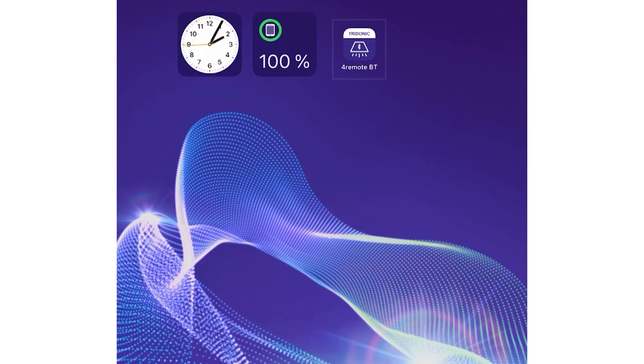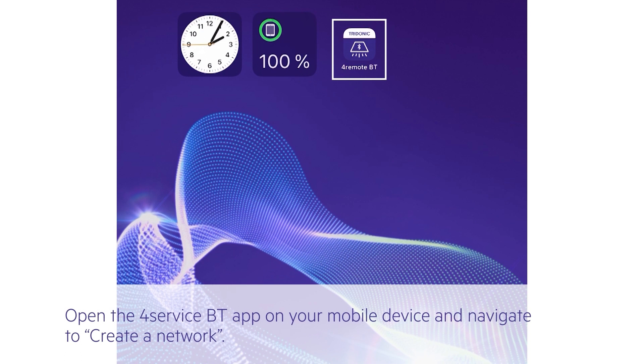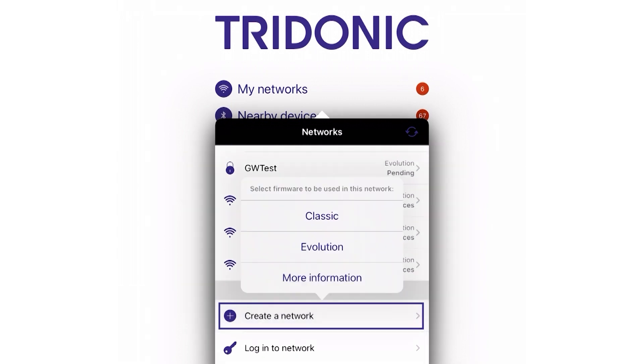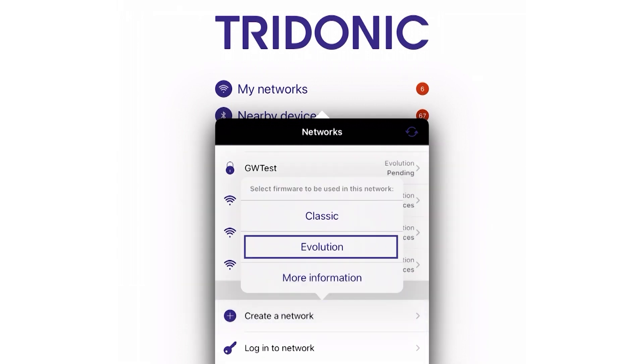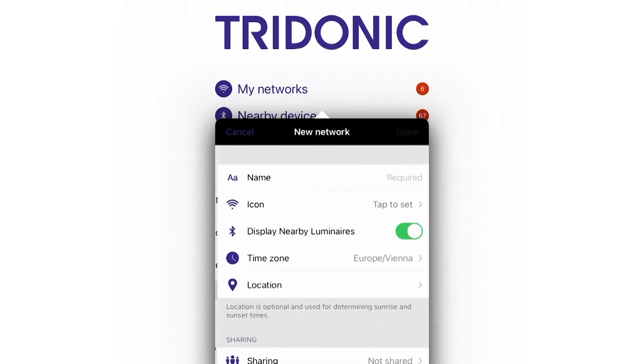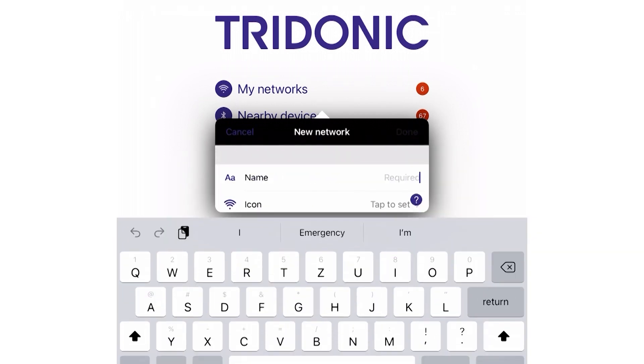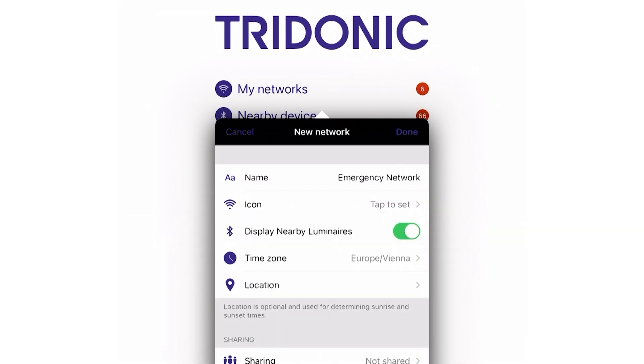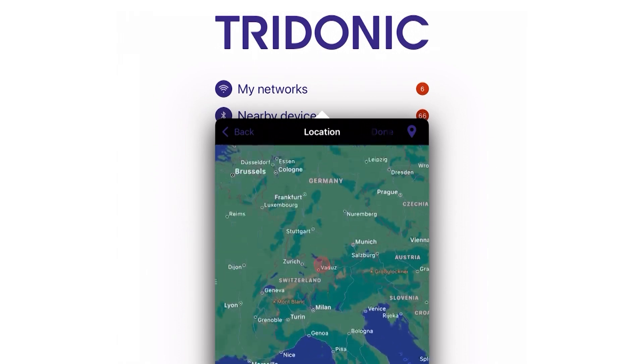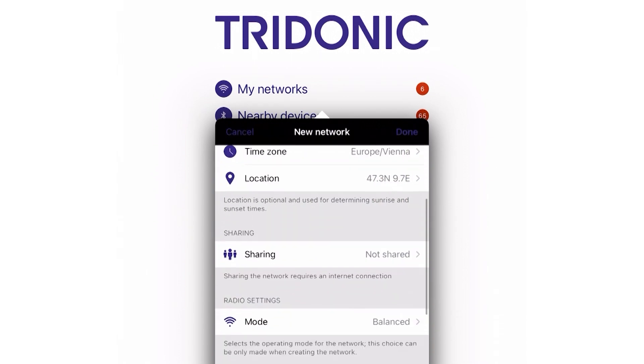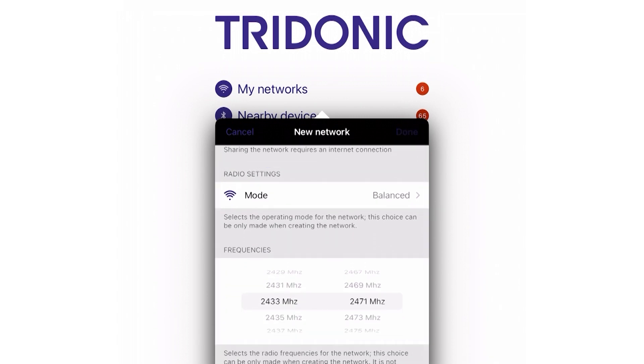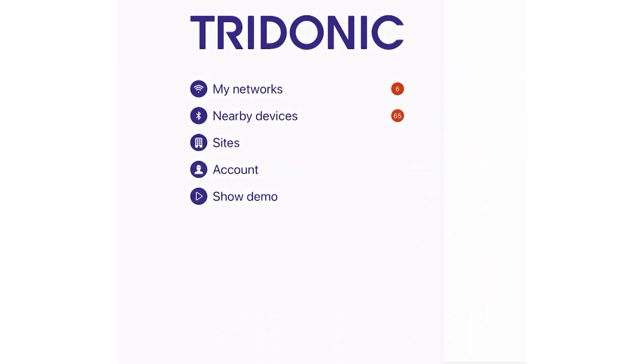First of all, it's necessary to create a network with all emergency devices of the system. To do this, open the 4remote BT app and navigate to create network. Due to the DALI gateway function, it's essential to choose the evolution network type. Type in your network name and do all the necessary settings. It's important to know that it's not possible to change the radio settings and frequencies afterwards. All other settings are changeable at a later point.